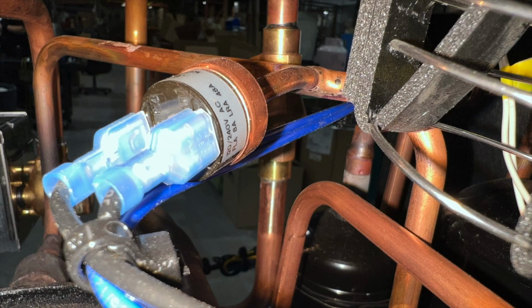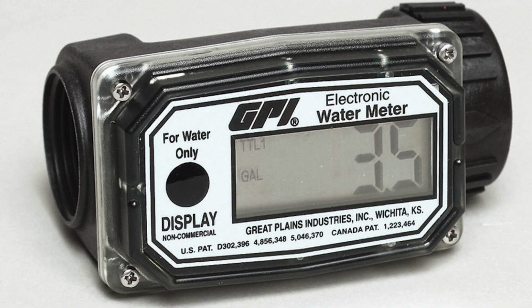Start by checking the continuity of the high pressure switch. It should be closed at a standing pressure of about 180 psi. Install a flow meter in one of the water lines. It really doesn't matter whether it's on the inlet or the outlet. Water flow will be equal in both directions. You should expect to see a flow rate of about 1.8 to 2 GPM per ton of cooling.